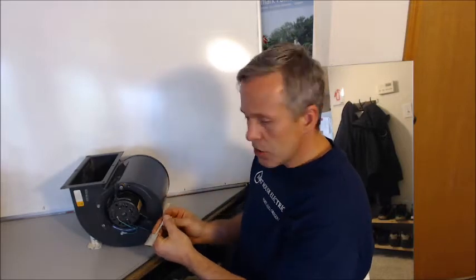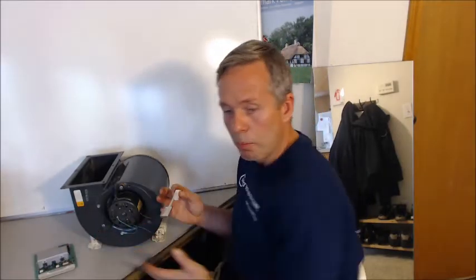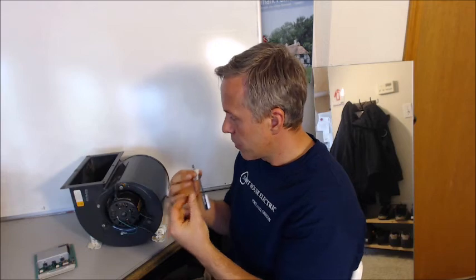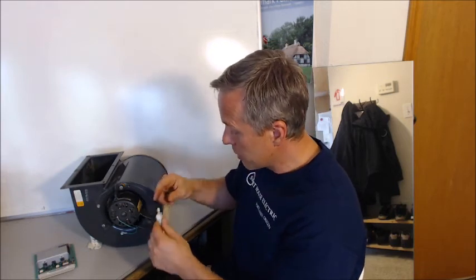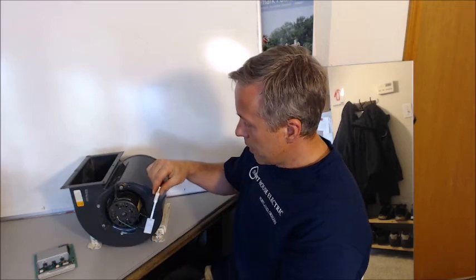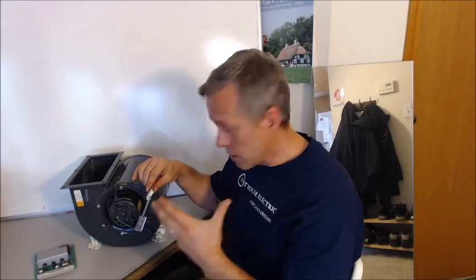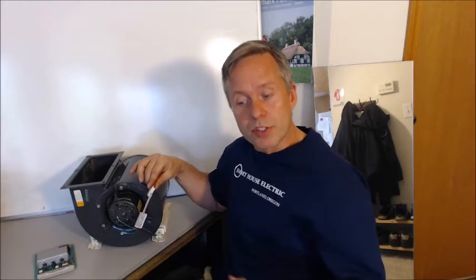I'm going to shut off and give the message on the display saying error code 40. What that can be related to is that it doesn't need to be that any of these components are failing. If your filters are so dirty that there is no airflow, so see the fan is spinning and everything, but there's simply no air coming into the bed because everything is closed, then there's not enough airflow for this to engage. So the first thing to absolutely check when you have an error code 40 is to make sure your intake filters are clean.